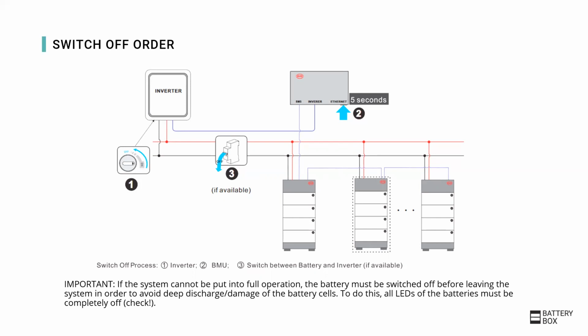As for the other premium batteries, if there are problems with the system and it cannot be put into full operation, it is very important to always switch off the battery completely before leaving the system. Here, all LEDs should be completely off. Also, the system should then be put into operation within a few days, or the service should be contacted. Please note that an improper handling can damage the battery.